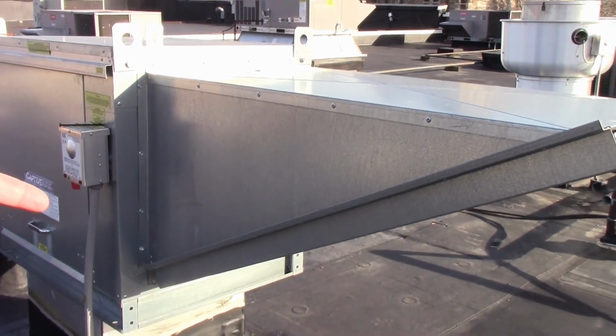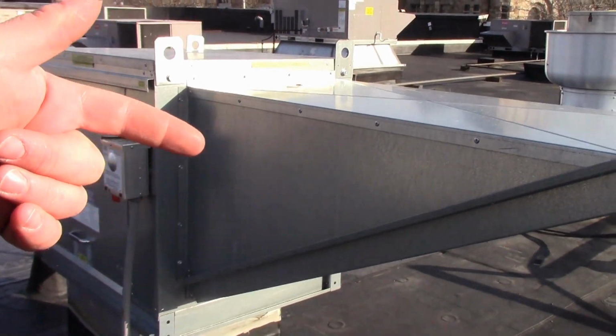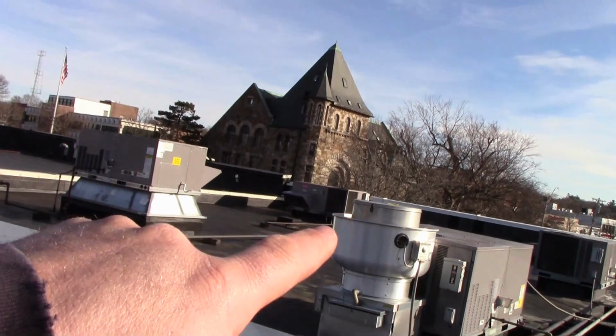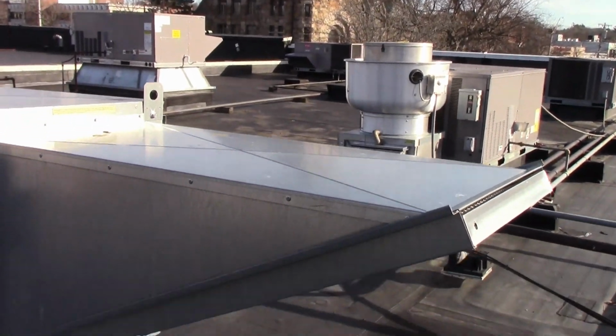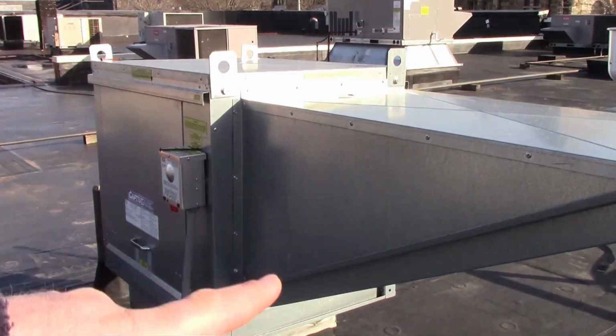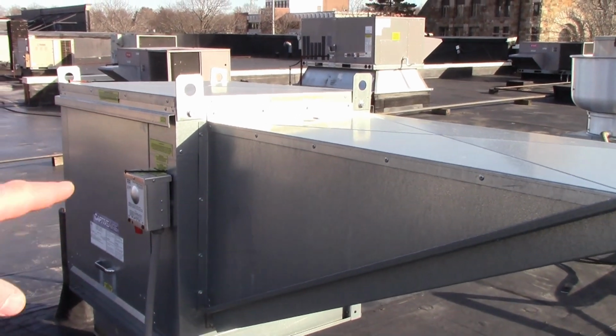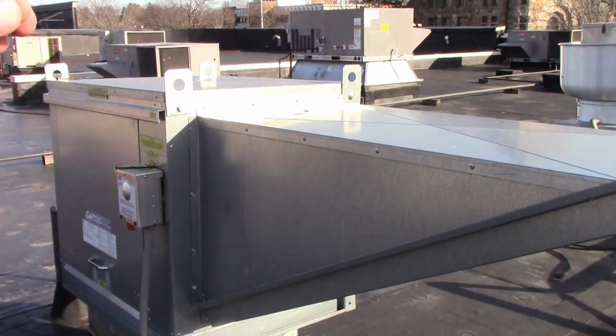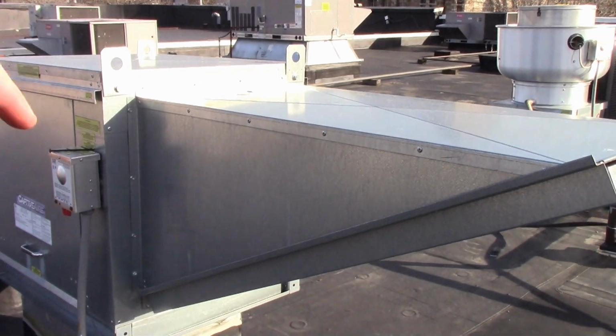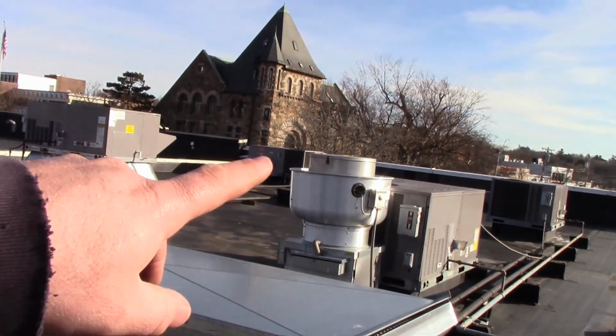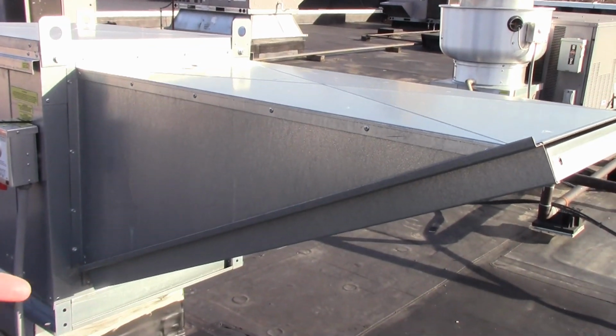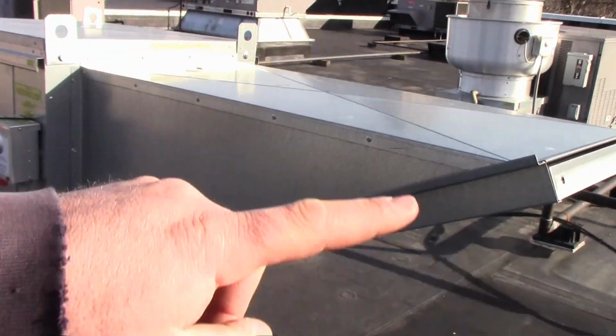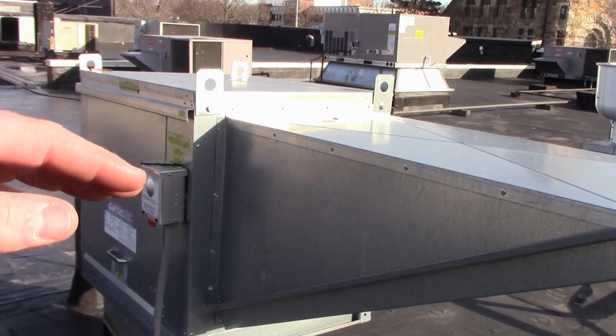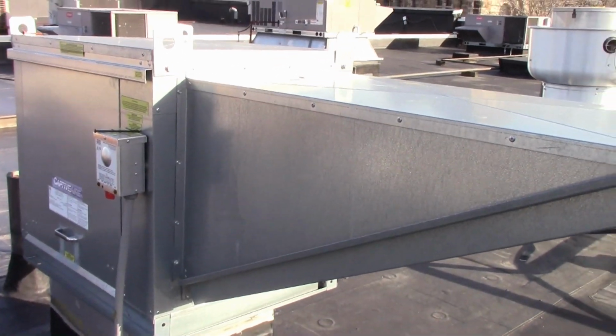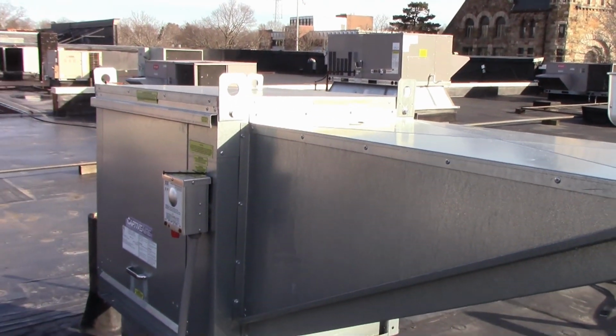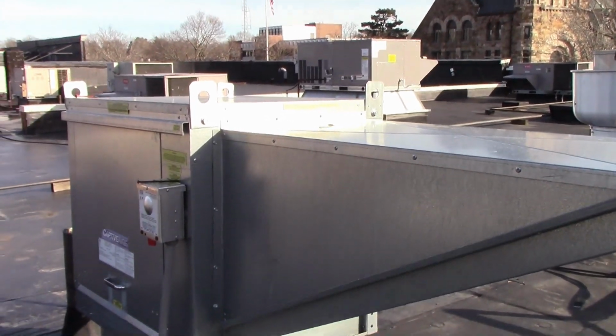So this is a makeup air. This is designed to put all the air back into the building that exhaust takes out. Problem with this setup is you can see this is unconditioned, which is fine. Usually when they do unconditioned makeup airs, they have the vents for it angled up towards the exhaust, so the cold air will come right into the building and go right back out. Well, not so with this one. With this one, the vents are right over where the cooks are standing on the cook line, so they're freezing their butts off. The only problem is with shutting that off.